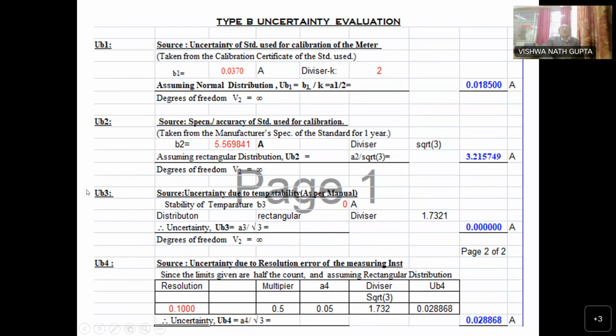So here is the source uncertainty of the standard used for calibration of the meter. Sir, again, as we discussed earlier, once we are using our calibration standard, the uncertainty from the SI units to the NPL to the ERTL should be transferred. So here UB1 uncertainty is 0.0370 ampere, as per the calibration certificate of our standard that we have got from the ERTL or NPL. These are defined by our calibration agency, that for this equipment you are uncertain of 0.0370 ampere at that range of the equipment.